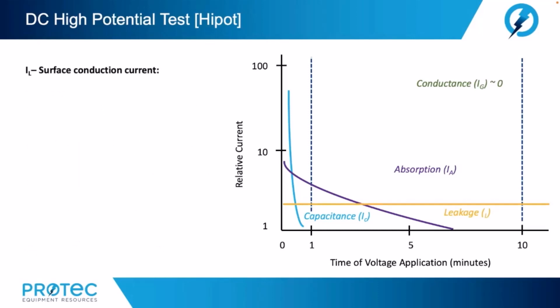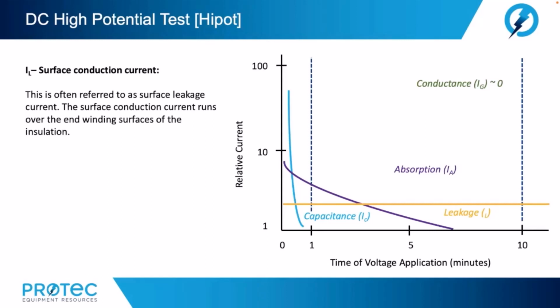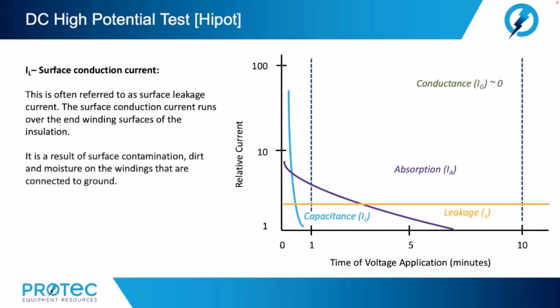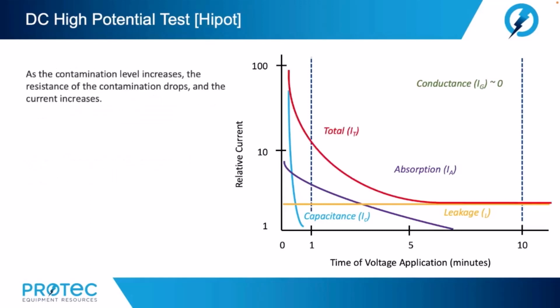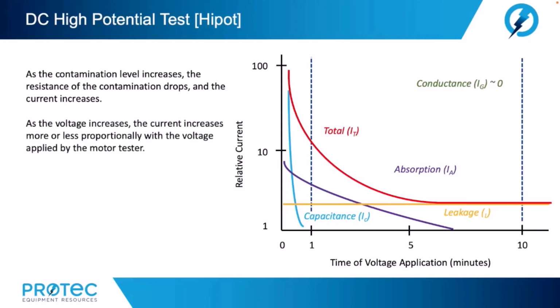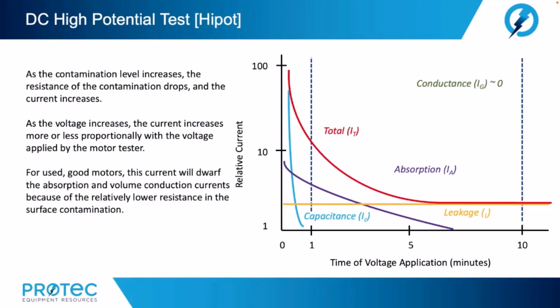And that is the surface conduction current. This is often referred to as surface leakage current. The surface conduction current runs over the end winding surfaces of the insulation. It is a result of surface contamination, dirt, and moisture on the windings that are connected to ground. As the contamination level increases, the resistance of the contamination drops and the current increases. As the voltage increases, the current increases more or less proportionally with the voltage applied by the motor tester. For used good motors, this current will dwarf the absorption and volume conduction currents because of relatively lower resistance in the surface contamination. For new, totally clean and dry motors, this current should be zero or near zero.